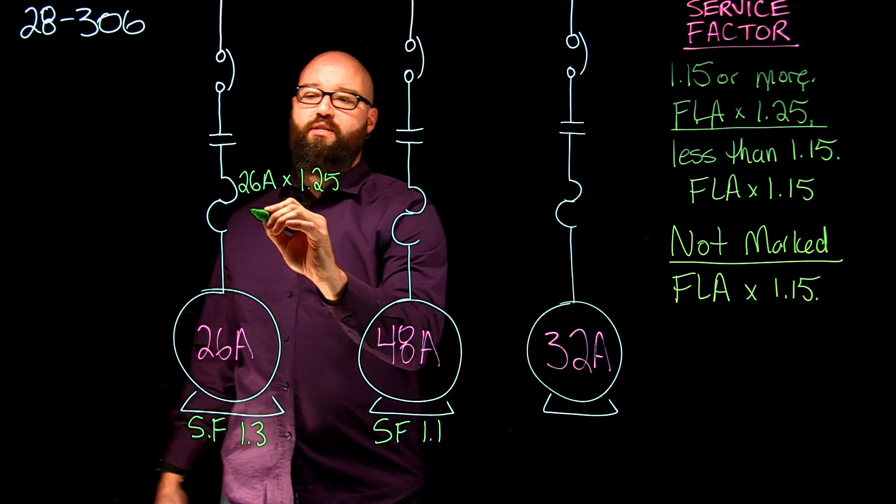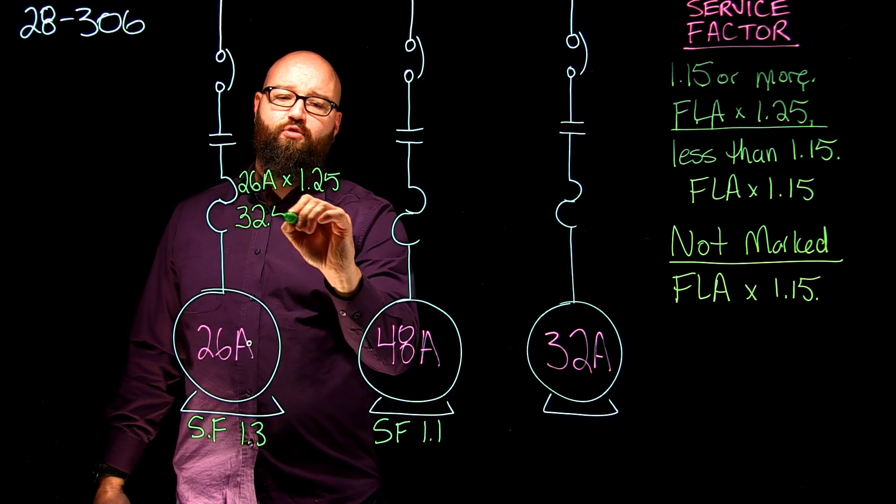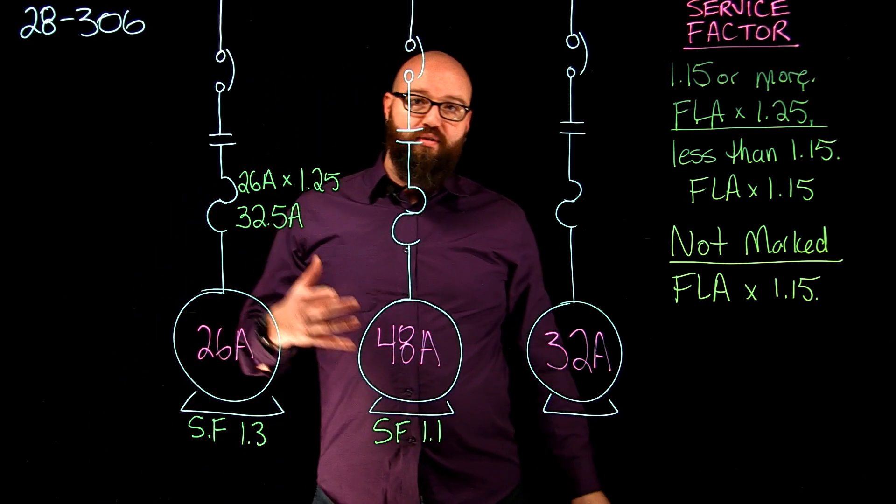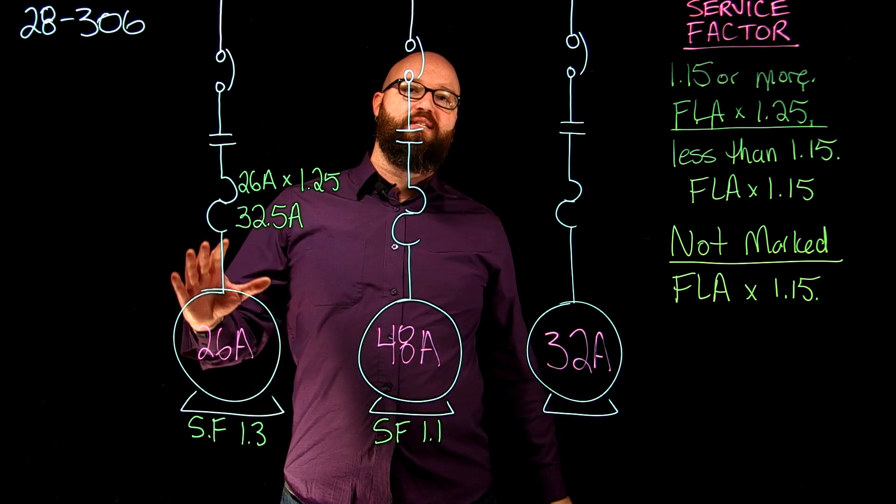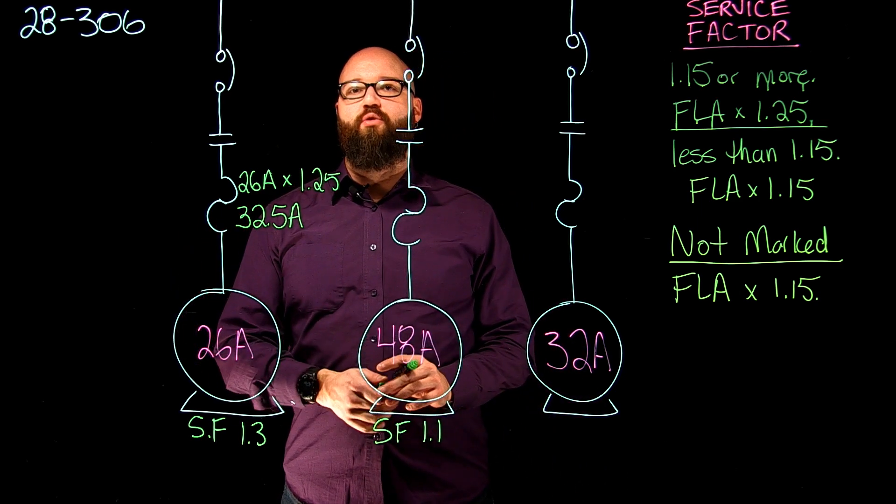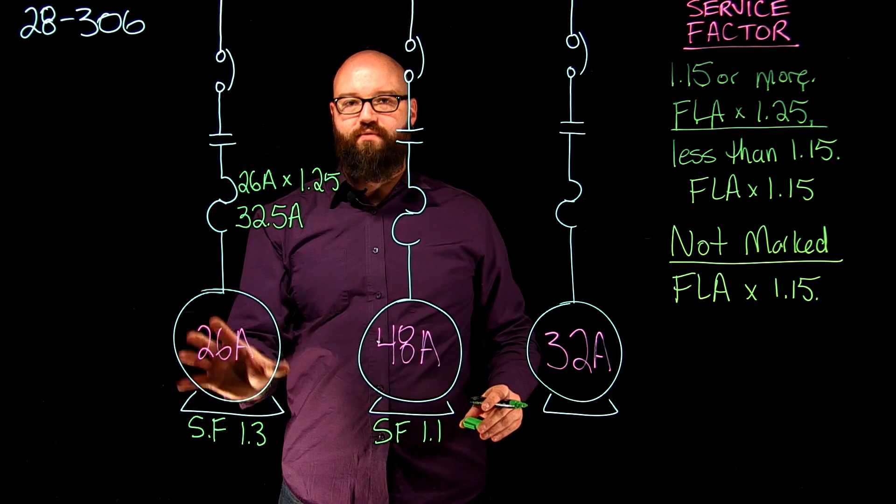Which should give us somewhere around 32.5 amps. And again, if I was able to adjust, this would be the maximum setting or calculated value of our overload device for this first motor.